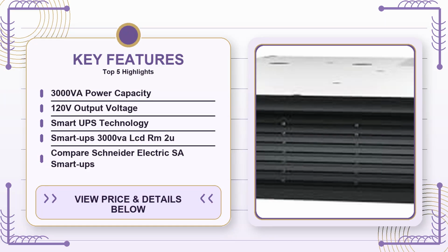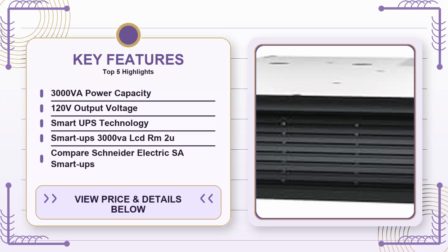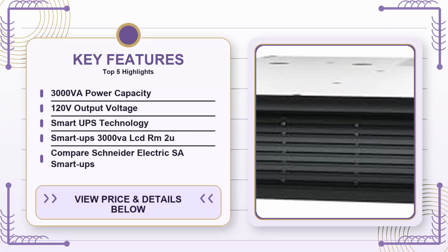One of the practical strengths of the Schneider Electric unit is its rack mount design. The 2U depth fits neatly into most standard 42U racks without forcing you to rearrange cable runs. The front LCD, while modest, gives you at a glance the input voltage, output load percentage, and battery charge status. That immediate feedback is a real time saver for sysadmins who are already juggling multiple monitoring tools. I've seen IT teams use that LCD panel to confirm that a newly added switch has not pushed the UPS beyond 70% load, a sweet spot that balances efficiency and battery life.